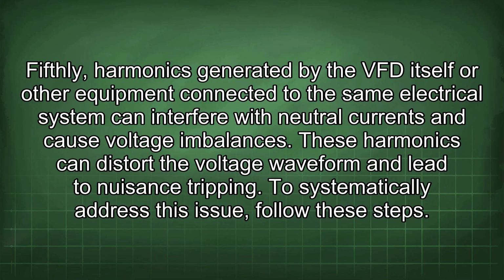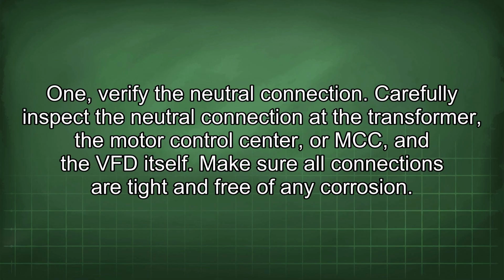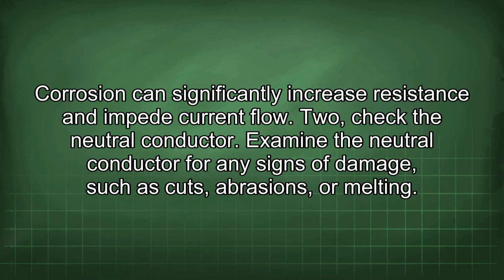To systematically address this issue, follow these steps. 1. Verify the neutral connection. Carefully inspect the neutral connection at the transformer, the motor control center or MCC, and the VFD itself. Make sure all connections are tight and free of any corrosion. Corrosion can significantly increase resistance and impede current flow.